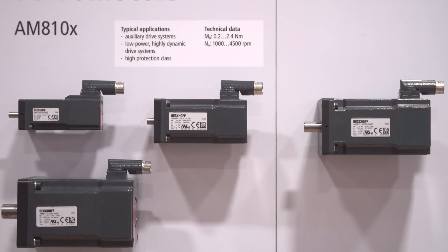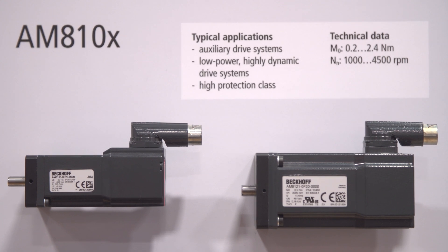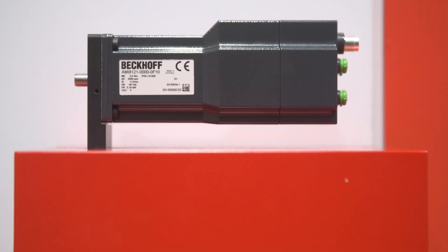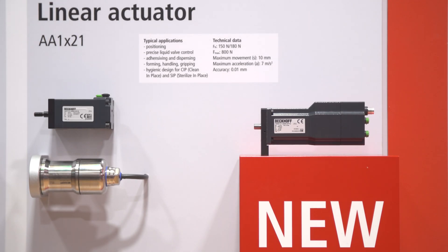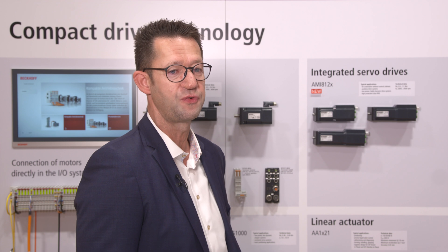The proven and tested motors of the AM8100 series, which have been on the market for years, have been extended by a servo output stage. This combination of motor with integrated servo output amplifier in protection class IP65 now enables customers to realize servo applications without control cabinets in the field of DC low voltage. All variants of this series are available with optional holding brake and integrated safety STO functionality via FSoE.